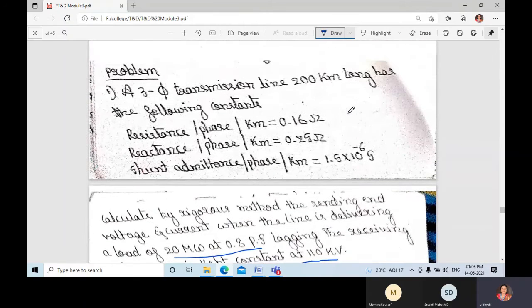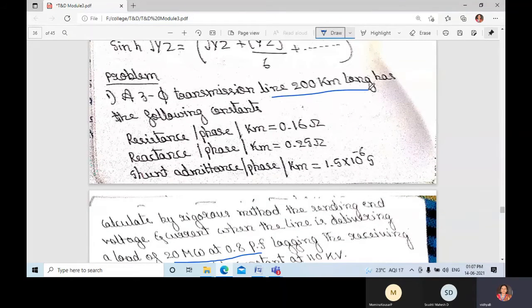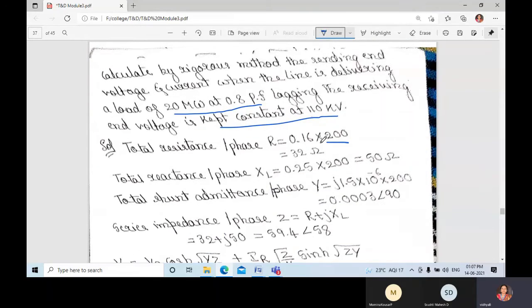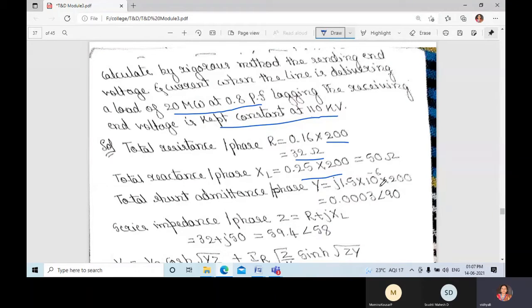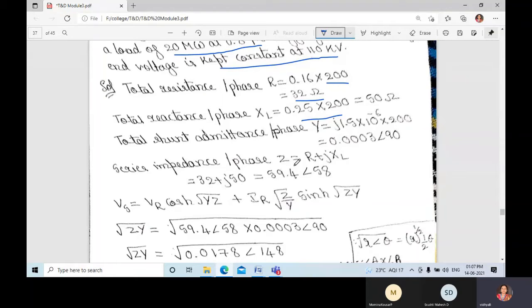Since values are given per kilometer, multiply by 200. So 0.16 into 200 gives 32 ohm resistance, and 0.25 into 200 gives the reactance in ohms. The impedance per phase Z equals R plus j·XL. Substitute the R and XL values and convert into polar form. The calculations involve complex equations which should be converted to polar form.